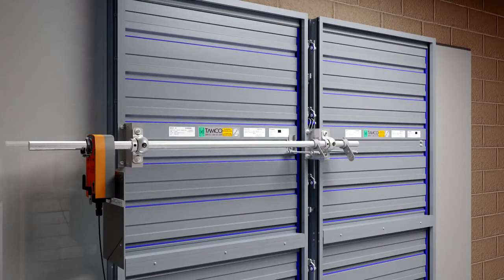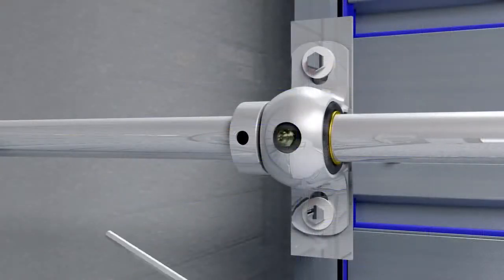If there is an obstruction, making it impossible to mount the actuator on the end of the jackshaft, it can be mounted in front of the damper. To do this, loosen the locking collars and jackshaft crank arms.